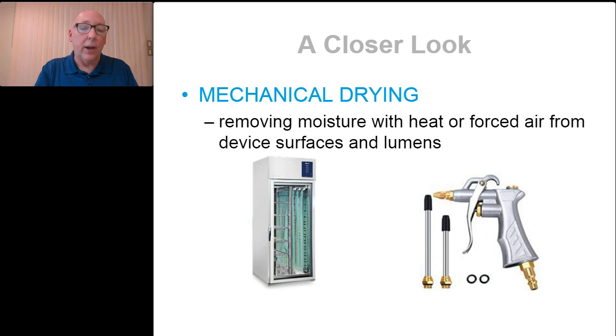So mechanical drying can enhance drying of surfaces and lumens by directing warm air around devices or through devices if that is accompanied with it. The compressed air that you use in your department is an example of mechanical drying. You know, we've all used those compressors with the nozzles at the end of it. That is a form of mechanical drying. Most effective for simply reducing moisture inside a lumen, but not great for drying. So in other words, they can remove a lot of that residual water that may be located within a lumen device, robotic device, or a scope, but not very good for actually rendering the device dry itself.